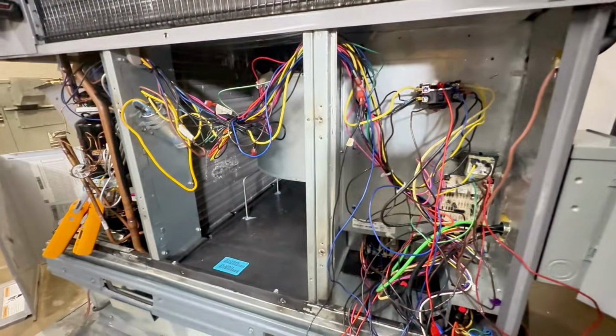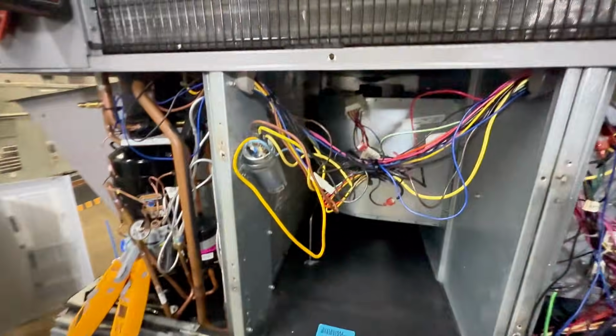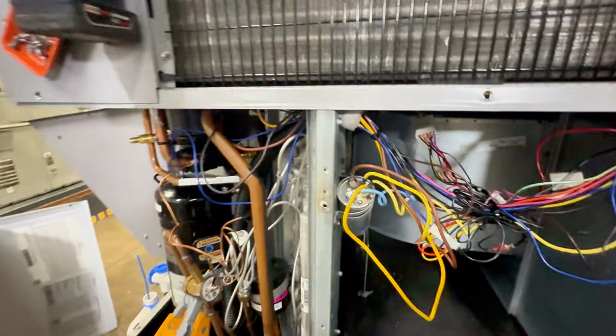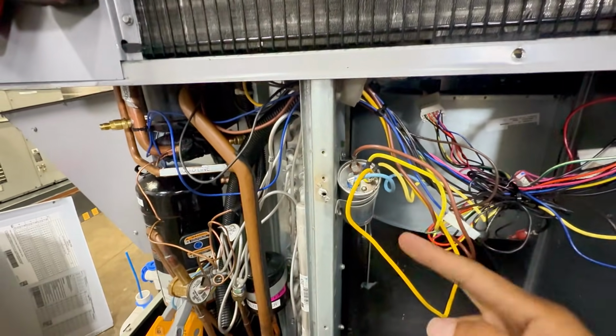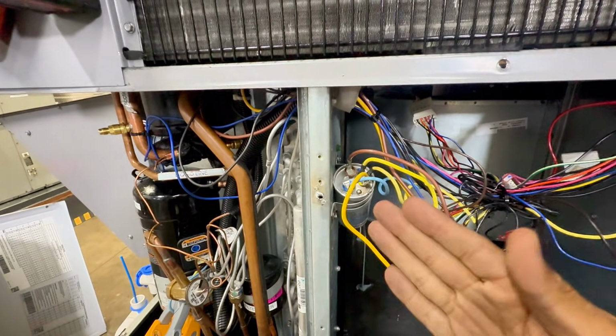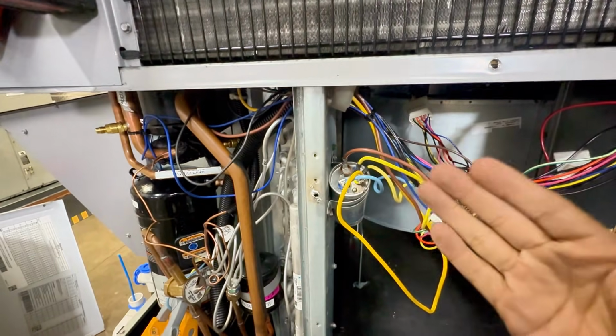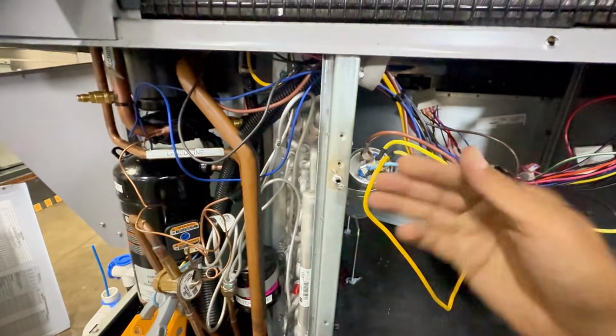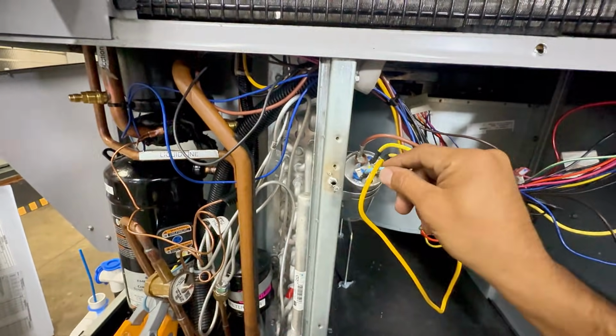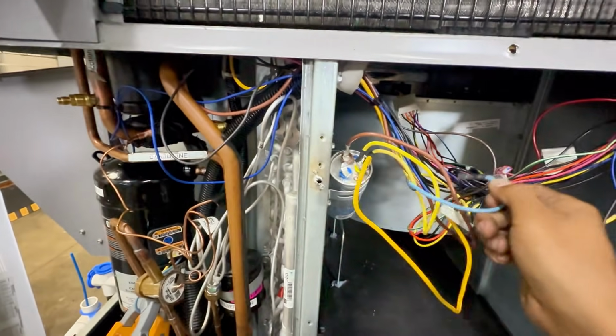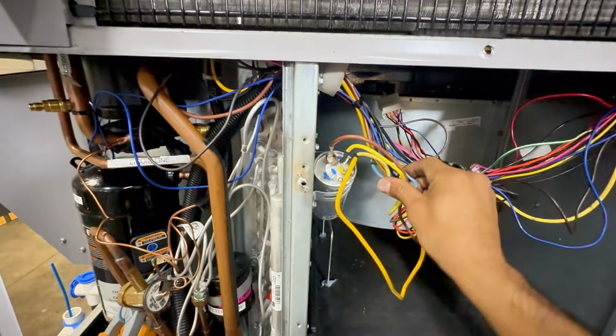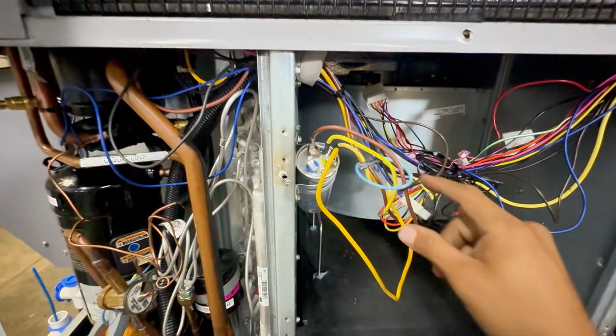Let me turn it off, because I'm going to be messing with the contactor. Remember, with single PSC, permanent split capacitor motors, you need a capacitor to create that 90-degree phase shift. Power's off, so don't think I'm doing this with power. But I remove the Herm. This is the power going to my start winding.